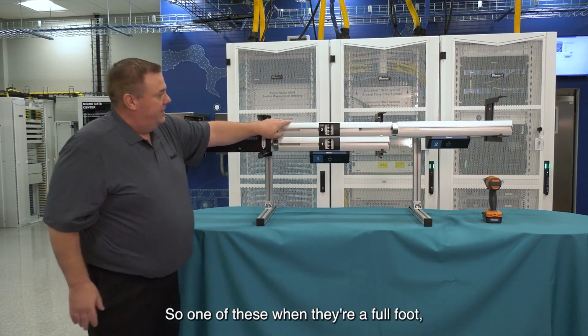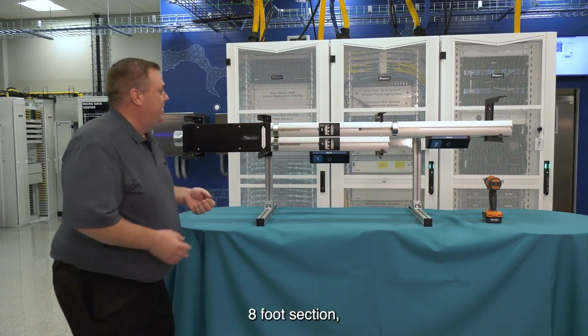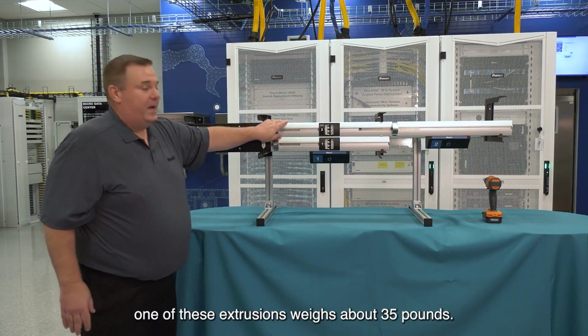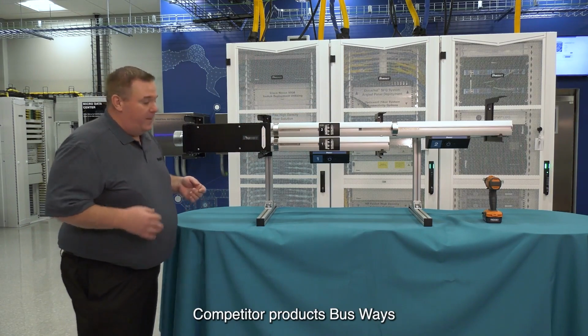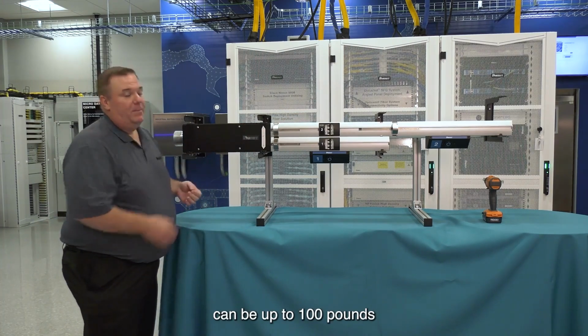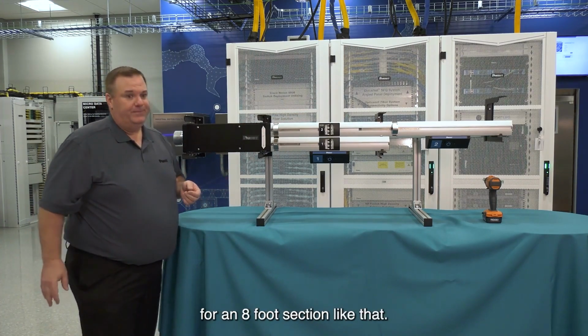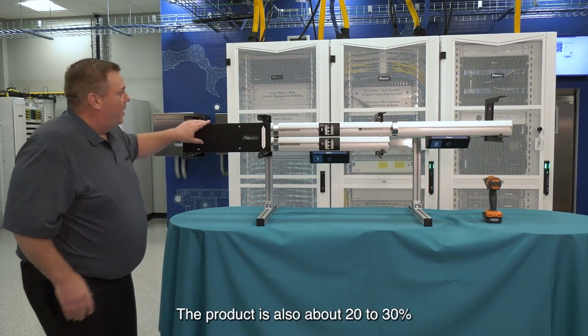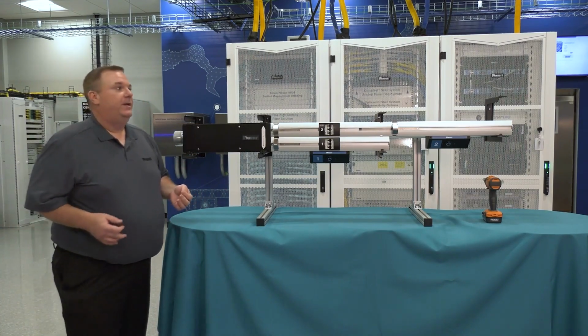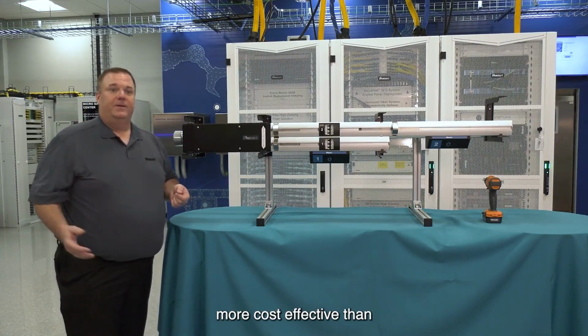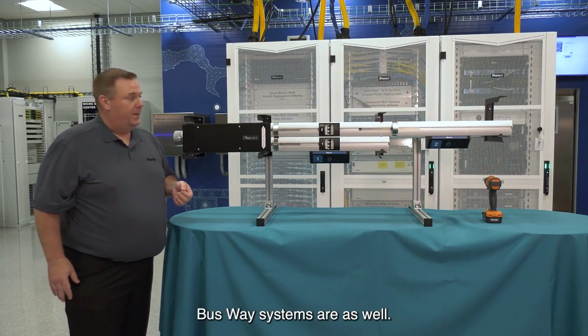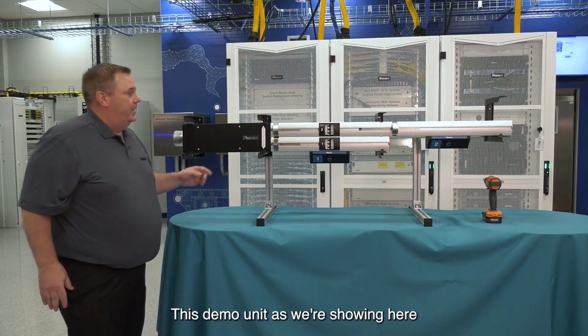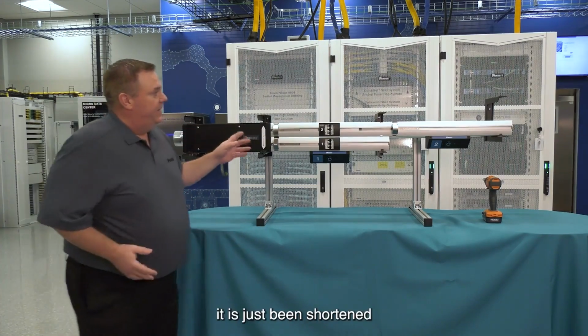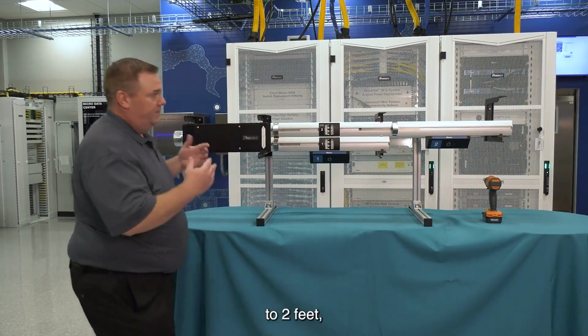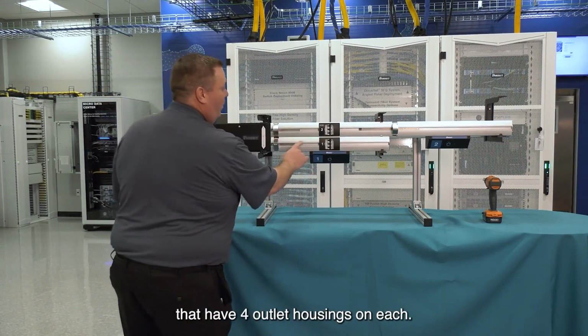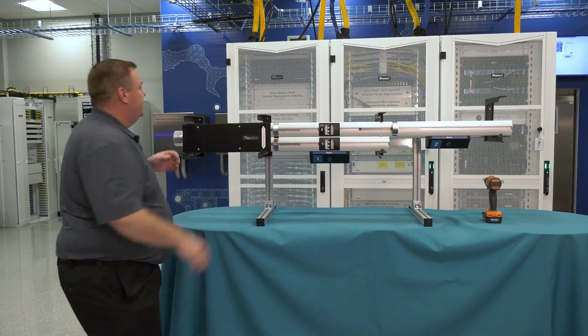So one of these full 8-foot sections, one of these extrusions, weighs about 35 pounds. Competitor products, busways, can be up to 100 pounds for an 8-foot section like that. The product is also about 20 to 30% more cost effective than busway systems. This demo unit has been shortened to 2 feet, but these are usually 8-foot modules that have 4 outlet housings on each.